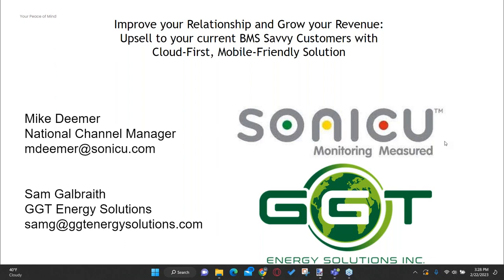If I could quickly add to that, as long as that account is current with Sonicu, with the Cloud Link or the SonicCloud application, all hardware is covered under warranty. And more importantly, as that NIST certification expires, we ship out a new sensor that's fully certified to replace that. So instead of putting it on a facilities team or third-party contractor to do field calibrations, if it falls into the NIST category, it's direct shipped to them for rapid deployment.